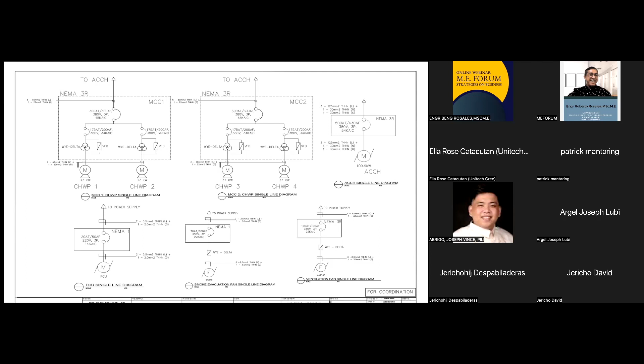Next, again, VFD versus soft starter. Like I said, we don't necessarily need the VFD for the system to work since we already have the Y-delta. But the real purpose of using the VFD is, aside from altering and controlling the frequency, the frequency also has a corresponding effect on the temperature difference. It adjusts your speed, so you can adjust the frequency and correspondingly adjust the speed.